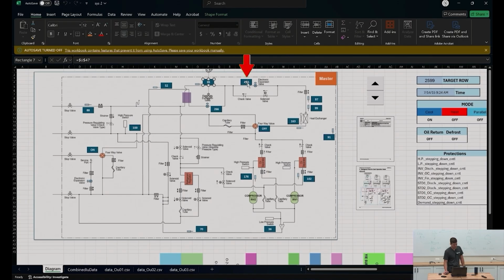Well, I'd either think it's the expansion valve in between these two or the filter that you see there. See that filter? This lets you correlate the two between it. Now I know when I go to that job, I'm not just checking the expansion valve, because the expansion valve checks good, and I just say, well, the only thing between here and here is the expansion valve, and it checked out good, it ohmed out good, it's modulating, I pulled it off, it's rotating like it should, it's not loud, it's not noisy, the seals are good. There's nothing else it could be.